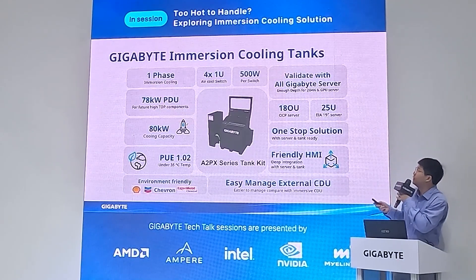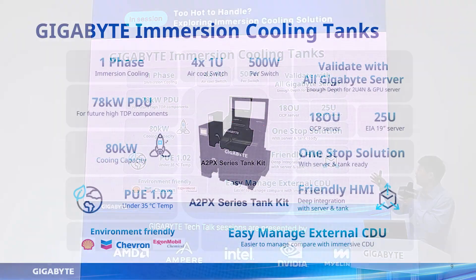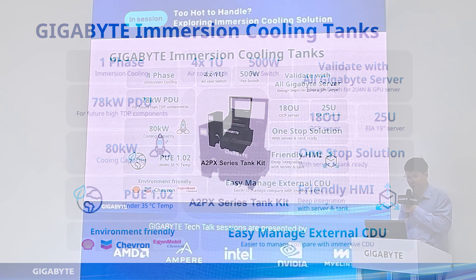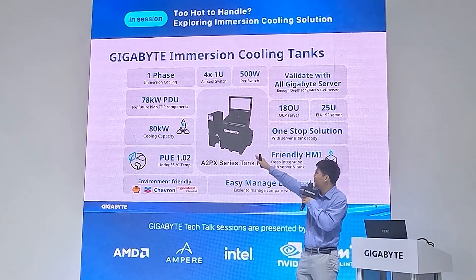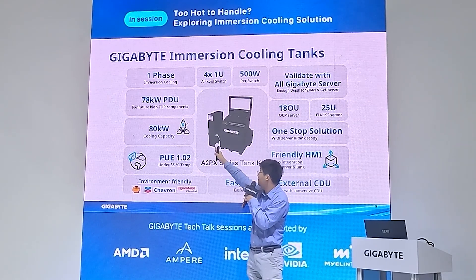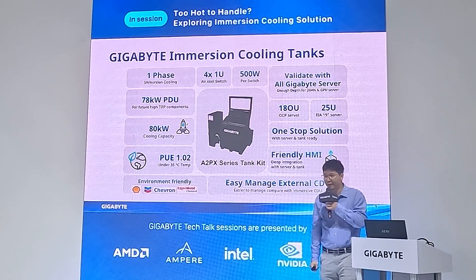This is the GIGABYTE immersion cooling tank. We have two types: the first is the OCP type, supporting 18U for OCP servers, and the other is a 25U EIA 19-inch type supporting EIA 19-inch servers. Cooling capacity is 80 kilowatts, and PUE is 1.02 with 35-degree warm water temperature. There is a friendly HMI to monitor tank status. Servers are immersed inside, while four 1U switches for air cooling and the CDU are placed outside for easy management.